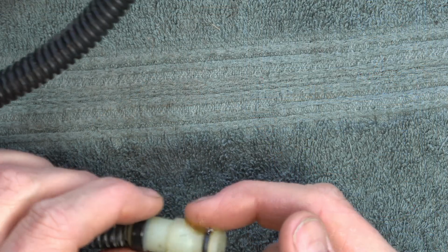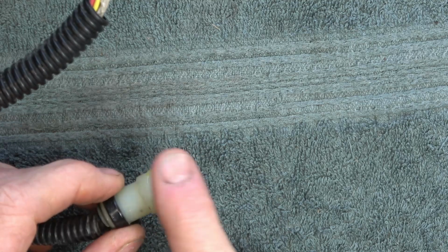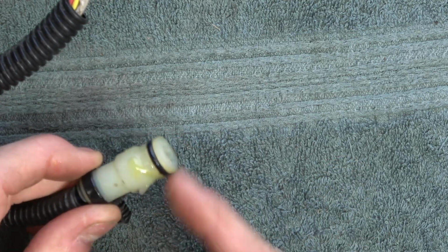I want to address the debate online about how to properly use dielectric grease. Many people think you should smear it around the sealing surfaces of the plastic connector, and that it will seal the connector from any moisture penetrating where the metal contacts are.